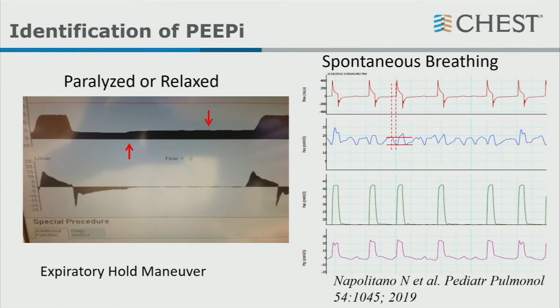And what we can do is look at where that baby starts to take the breath, or at least wants to start to take a breath, and there's a trigger delay here. So we see that there is the delay, and then we can look at the pressure difference between those two, and that pressure difference is the intrinsic PEEP the baby has to overcome in order to trigger the ventilator. And we can set the ventilator with that in mind as we work on getting the baby's lung disease better.